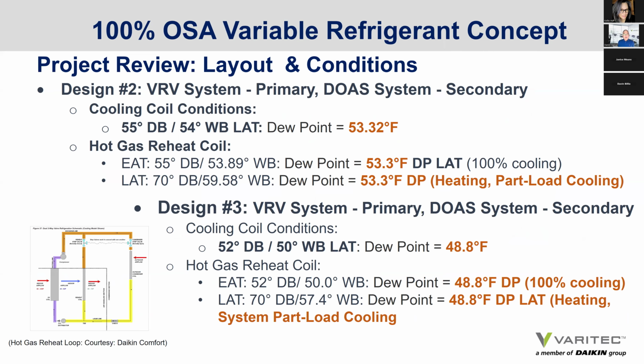So if we look at system design concept two with the 100% outside air unit, beware that we used a hot gas reheat coil to elevate the leaving air condition out of the unit to 70 degrees or load neutral. But if you look, the dew point remains at 53.3 because we're only adding sensible heat energy to the air coming off the cooling coil to bring us to load neutral condition. In design three, we did the same thing, but look at the dew point because we actually provided air at 52 degrees, 50 degrees wet bulb off the coil. And that was a target temperature that I didn't come up with arbitrarily.